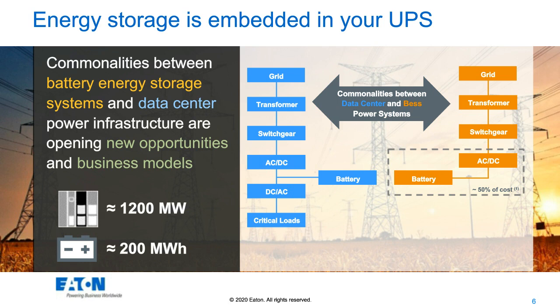And note that I could superimpose that directly on the blue blocks on the left. In other words, if I already have a UPS and battery, I might need a bigger battery for energy storage, but I already have most of what I need to allow the system to function as both IT equipment power backup and possibly an energy storage system with a longer battery. So that's a significant realization when data center clients and other mission critical clients are contemplating the use of an energy storage system.